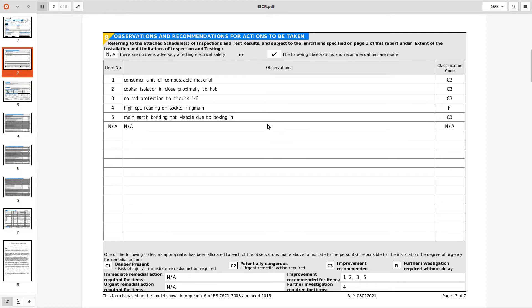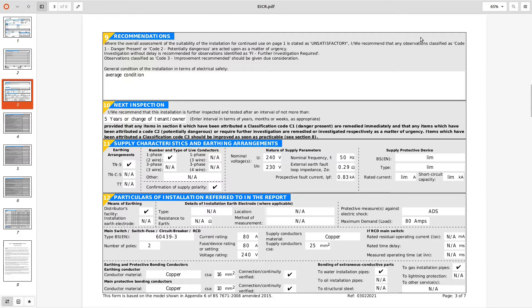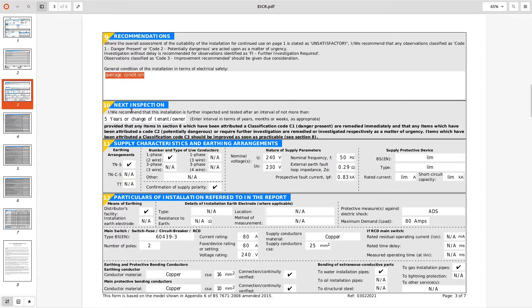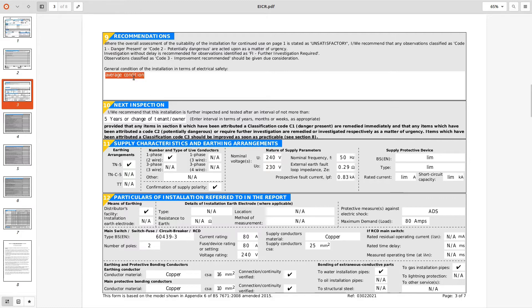So interesting, move on to page 3 recommendations. Now this is a really important box where we get to expand on what we've learned from the installation, what we think about it. We can't put average condition, we can't put good condition, excellent, because that doesn't tell people what condition the electrical installation is. If I put excellent condition and somebody else comes along their expectations of excellent will be different to mine, and average is again average condition, who knows what that means.